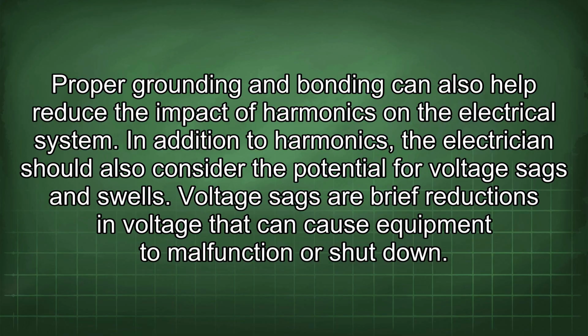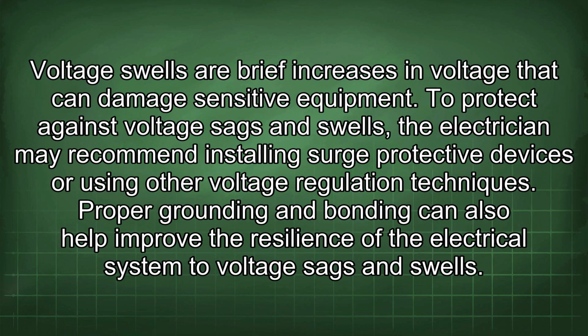In addition to harmonics, the electrician should also consider the potential for voltage sags and swells. Voltage sags are brief reductions in voltage that can cause equipment to malfunction or shut down. Voltage swells are brief increases in voltage that can damage sensitive equipment. To protect against voltage sags and swells, the electrician may recommend installing surge protective devices or using other voltage regulation techniques. Proper grounding and bonding can also help improve the resilience of the electrical system to voltage sags and swells.